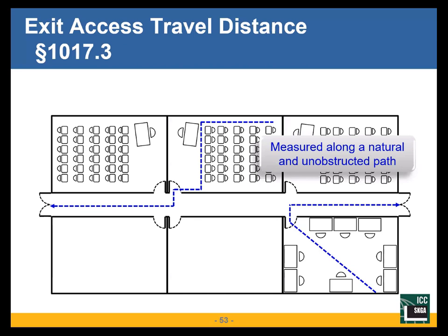Convince me that that's the path that they're going to take. Well, we've designed this. That's the only place we can put these desks because that's where all of our connections are. They're attached to the wall. They're built in place. They're okay. I'll buy it then. But you've got to convince me that that is in fact the natural path. That it's this way at certificate of occupancy, and it's this way next year because I've changed my exit path. I cannot go from here to here.